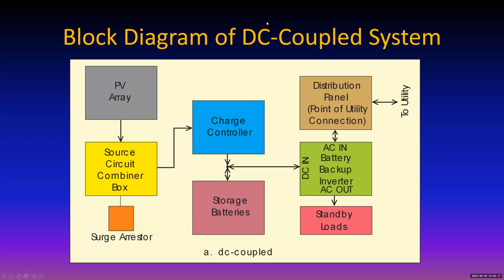Here's the question. Let's see what we got. How do you preclude second and fifth harmonics in the green box? For the most part, they are filtered out with inductive and capacitive filters. Generally in the green box, the basic sine wave is generated with a pulse type system, but then the pulses are smoothed out to the extent necessary in order to meet the second and fifth harmonic requirements of UL 1741.